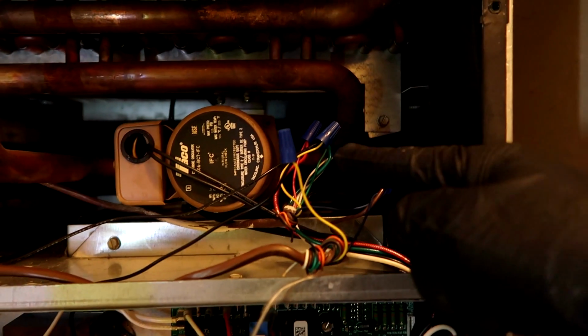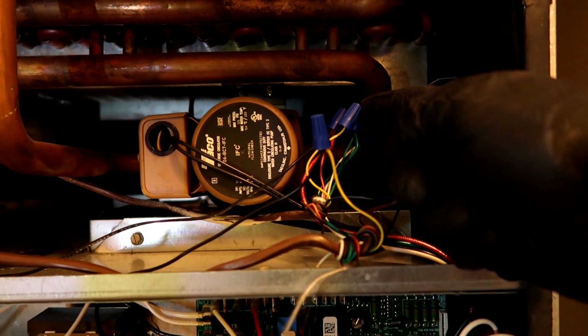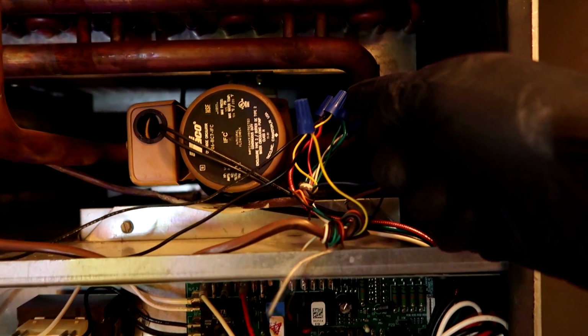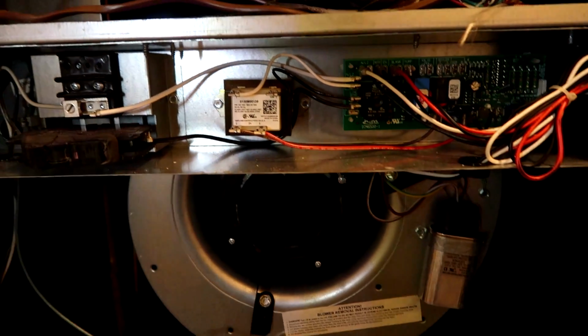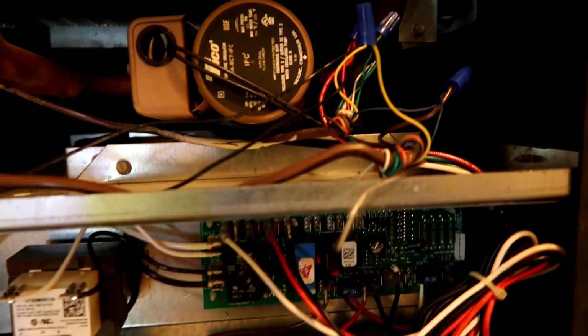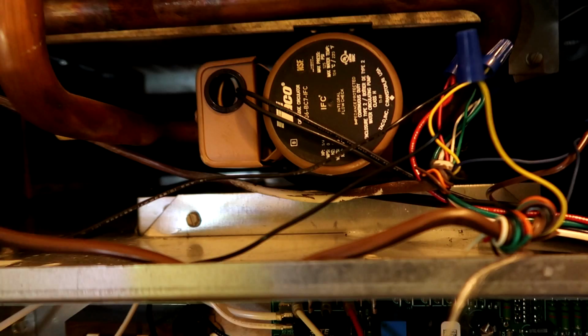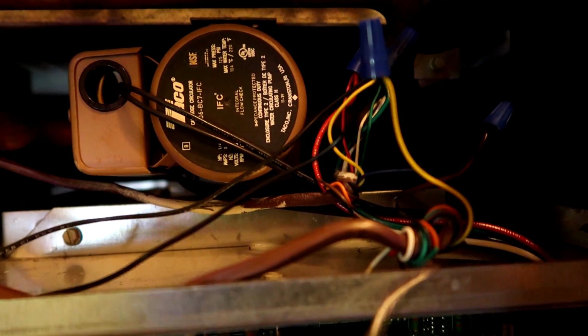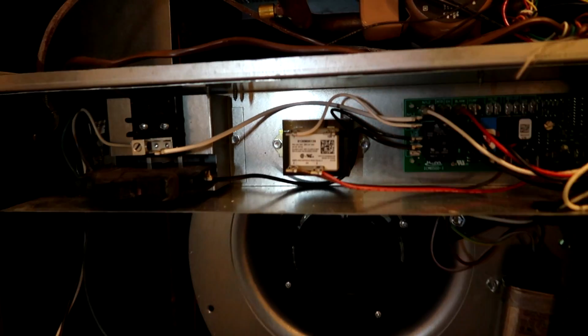They jumped out yellow for the float switch. So that'd be for the condenser, not the inside. So if it was the float switch, the inside would still come on because they have yellow jumped out on the float switch. Man, I came back in, I could smell something.